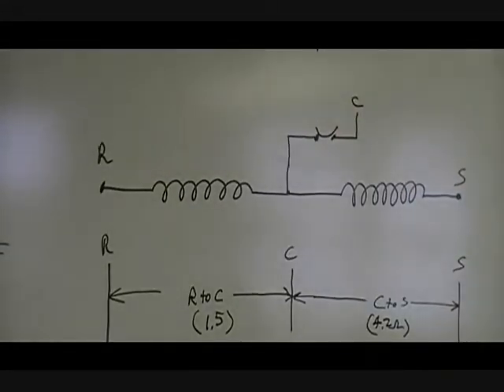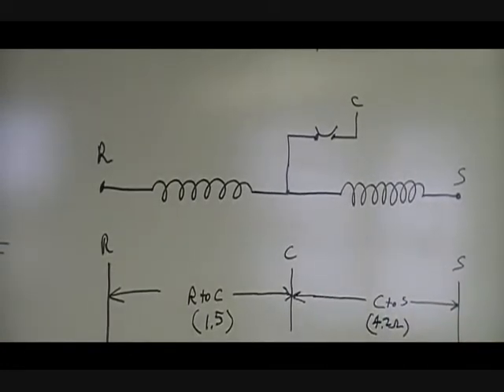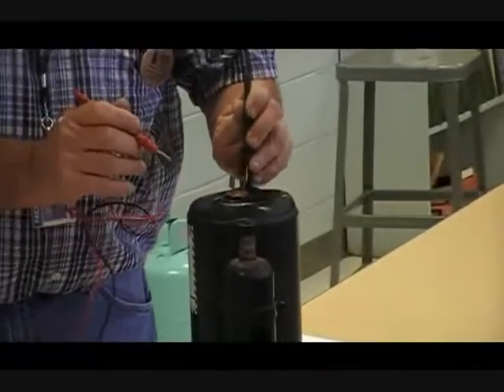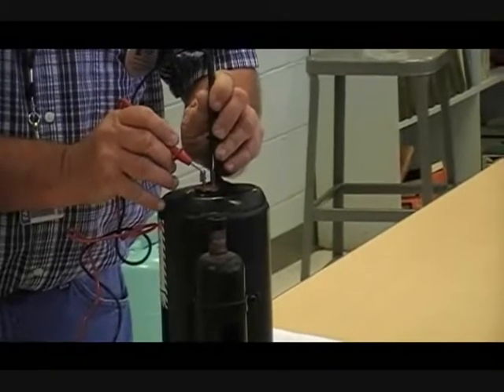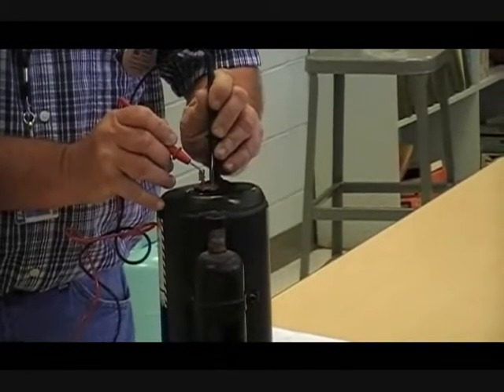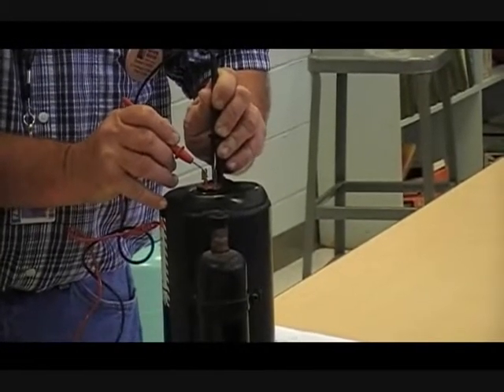We can determine which terminal is which by measuring a compressor. If you'll look at what I'm going to do, I'm going to take a look at my three terminals and I'm measuring the resistance. Here, I have 5.7 approximately.